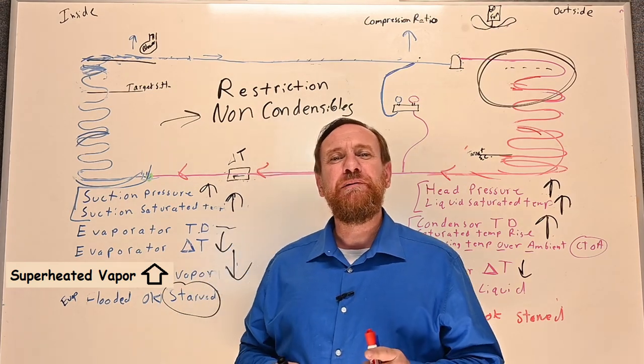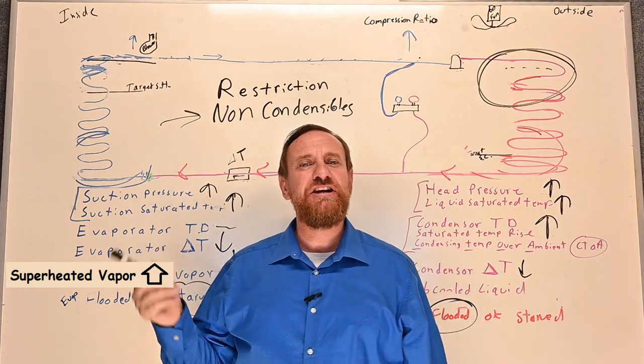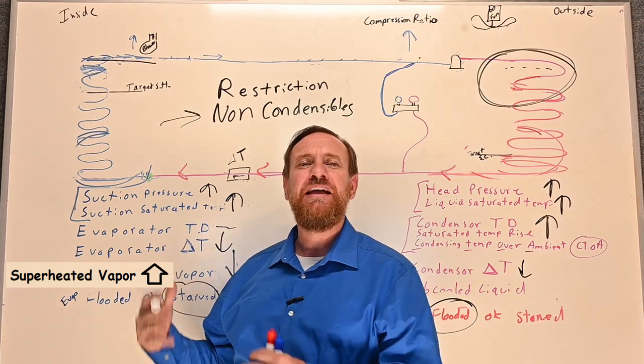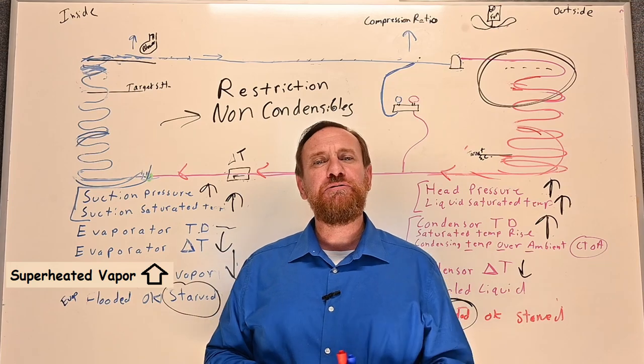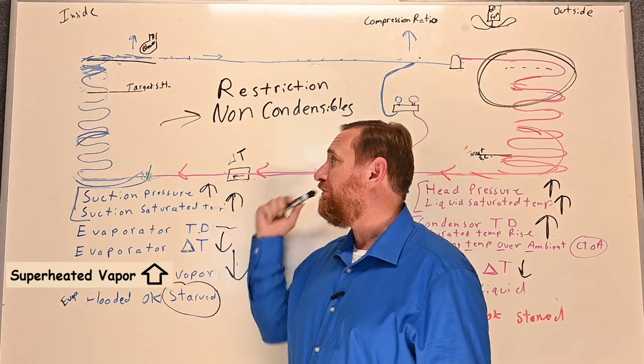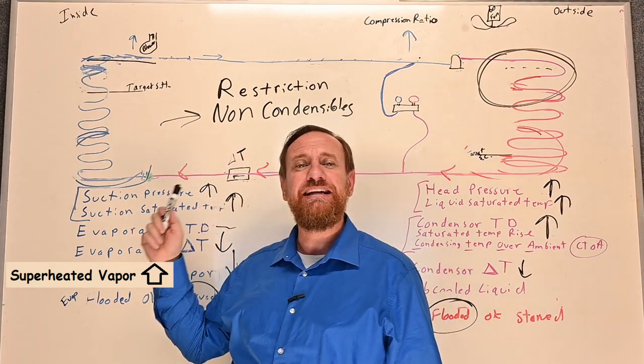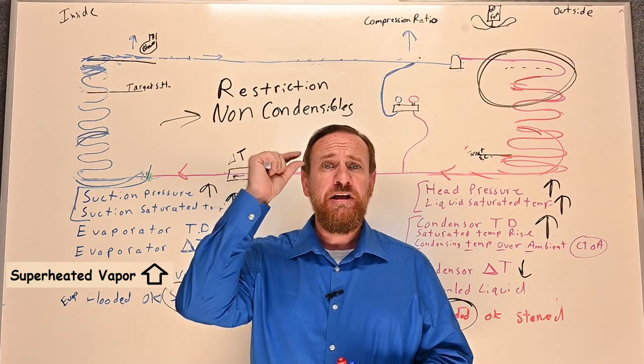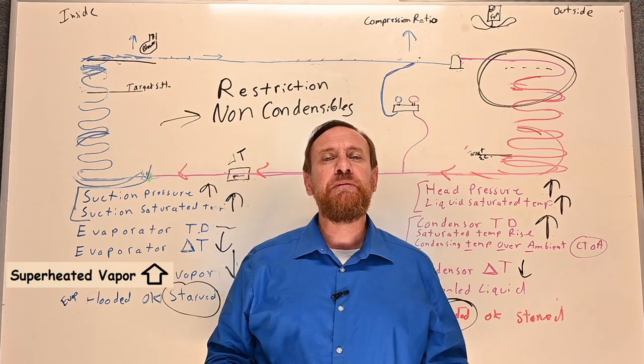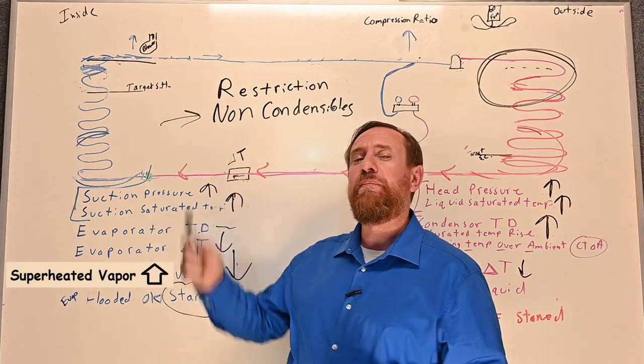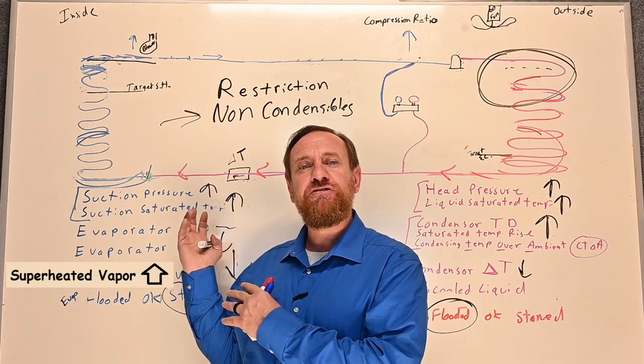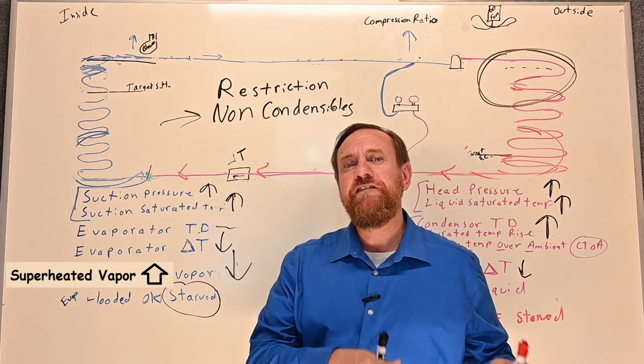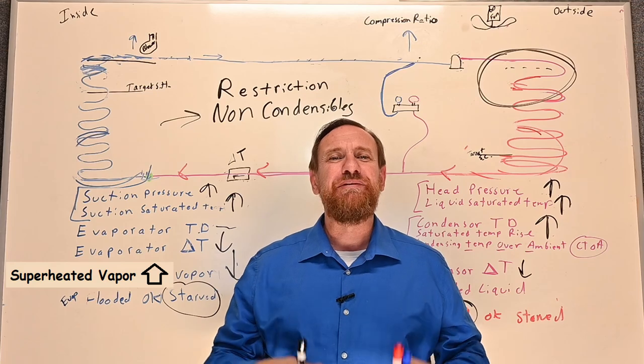A lot of people want to put the existing refrigerant back in if it checked out okay — but don't do that. Always use new, fresh, virgin refrigerant. Even if it matches the temperature-pressure chart, you don't know what other contaminants are in it. The labor to recover, inspect, pressure test, and recharge is a significant cost. The cost of refrigerant is small compared to all that labor. Legally, you can put refrigerant from a single customer's system back in using its own dedicated tank, but it doesn't mean it's a good idea.